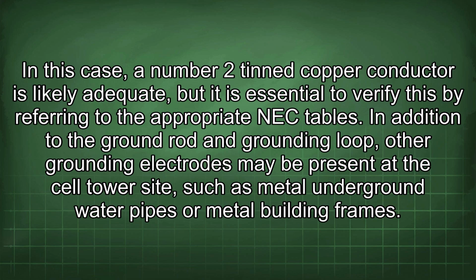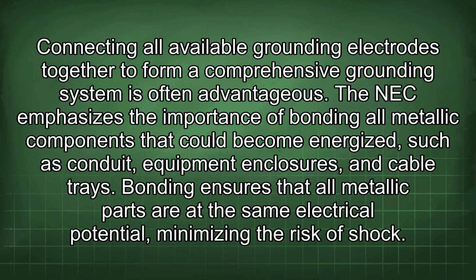In addition to the ground rod and grounding loop, other grounding electrodes may be present at the cell tower site, such as metal underground water pipes or metal building frames. Connecting all available grounding electrodes together to form a comprehensive grounding system is often advantageous.